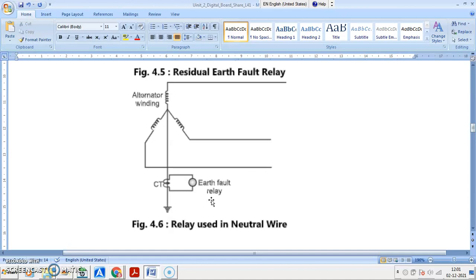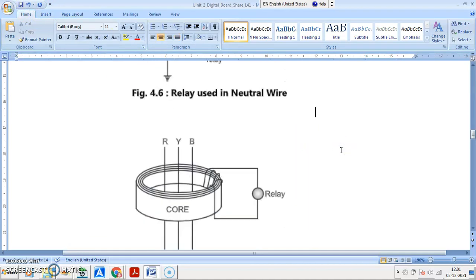So this is called unrestricted earth fault protection. There is no restriction particularly. Whenever current flows through the secondary, the relay operates. Whenever current increases through the earth circuit, the relay operates. Okay. Any doubt? If you have any doubt, you can ask.